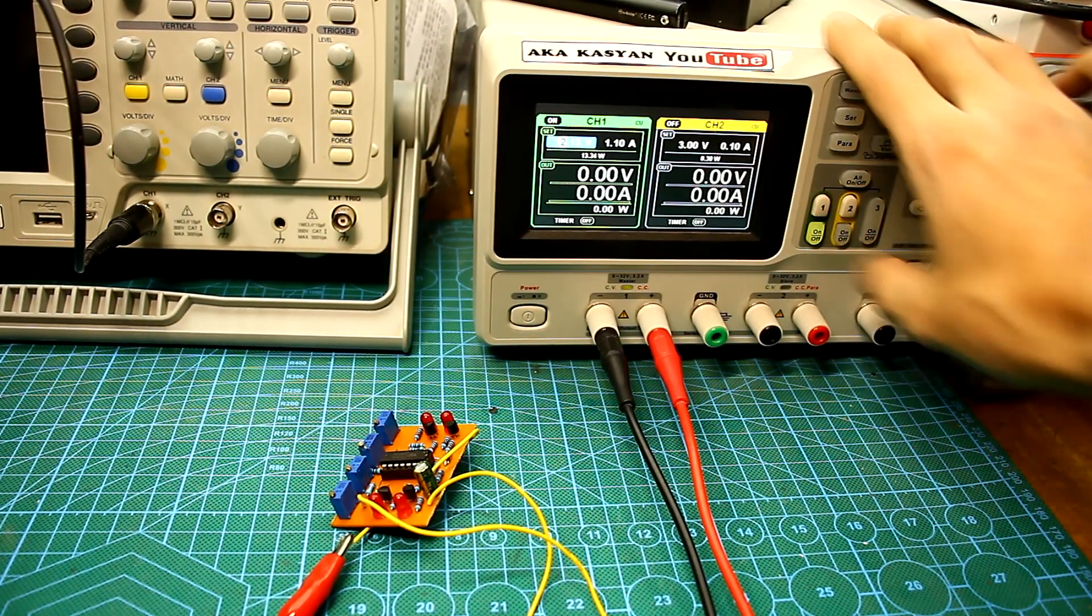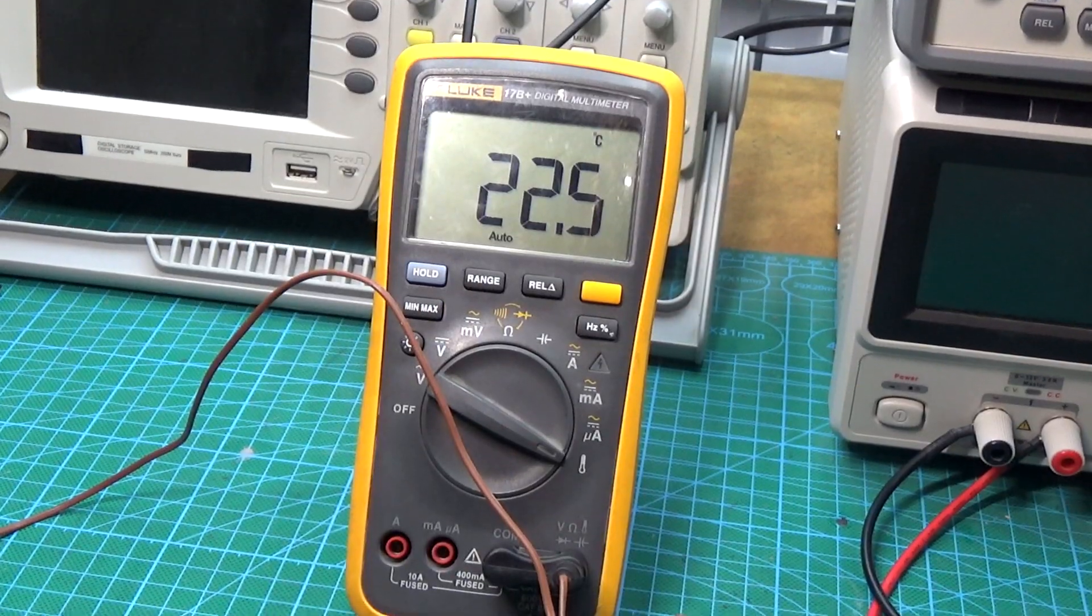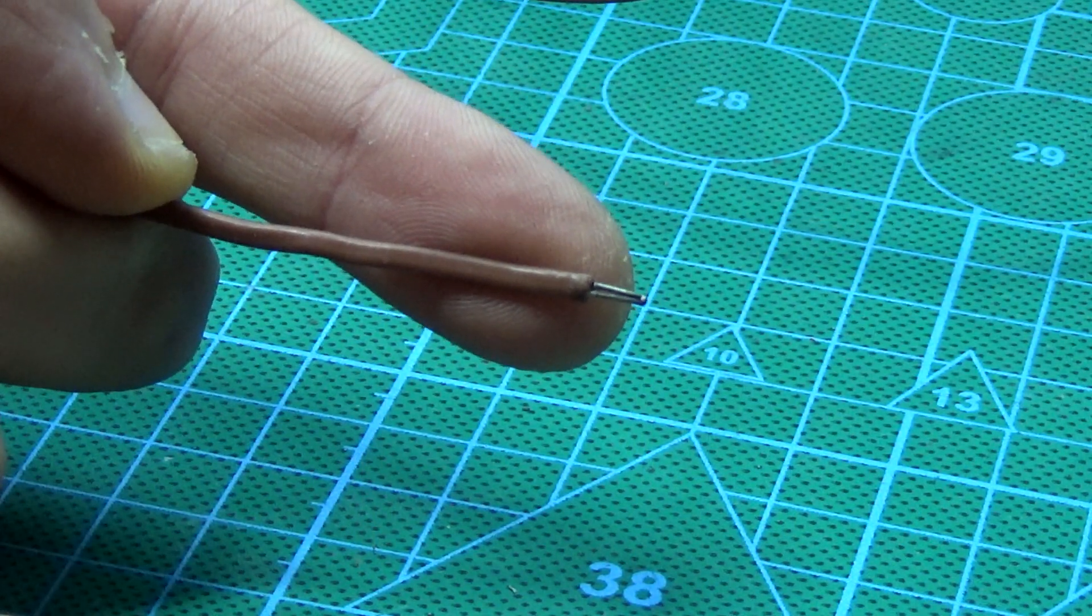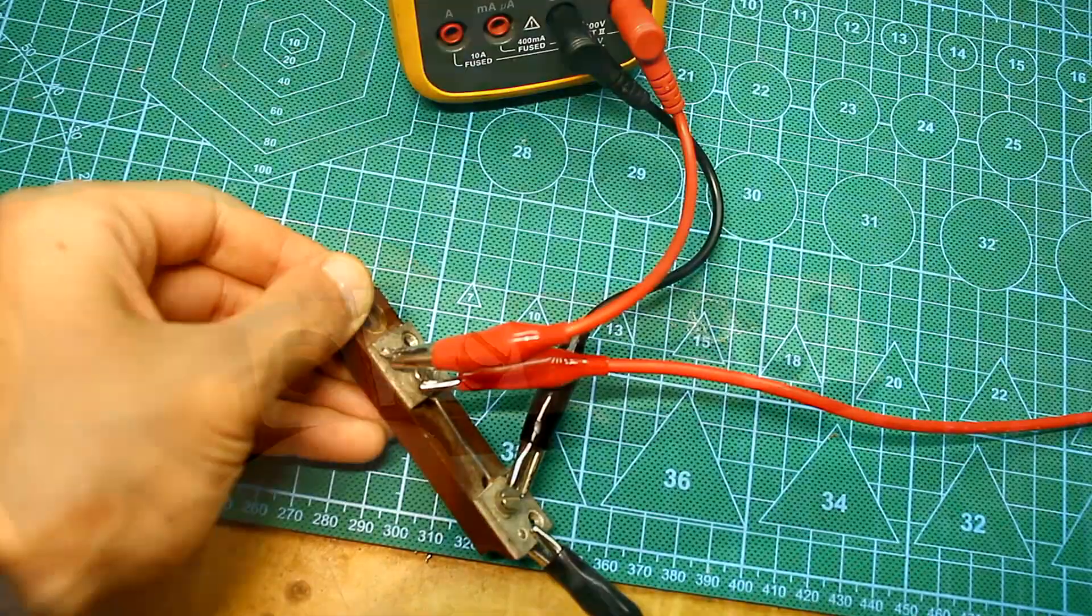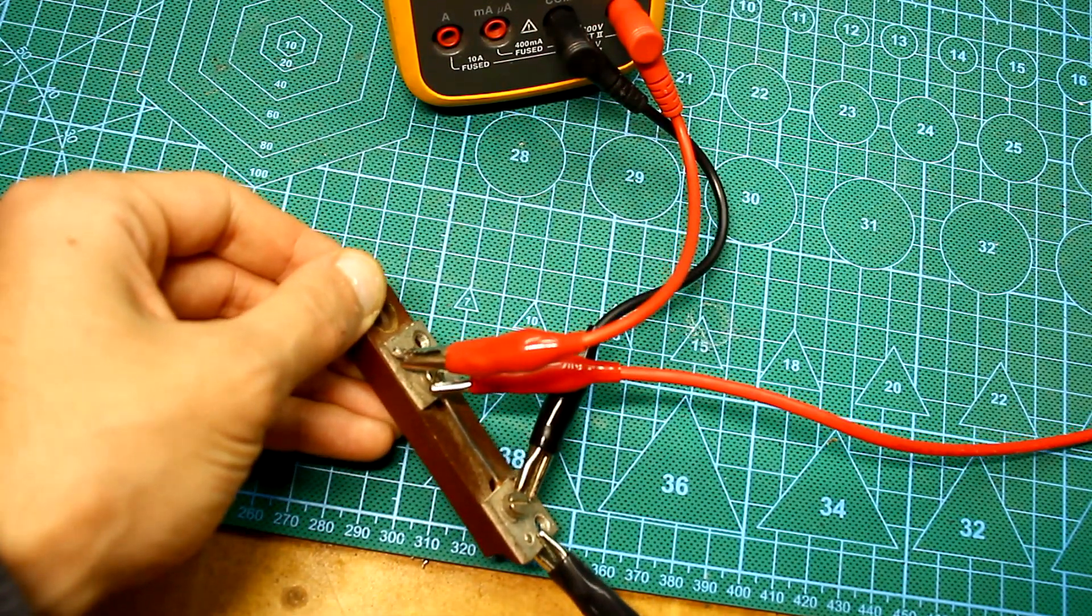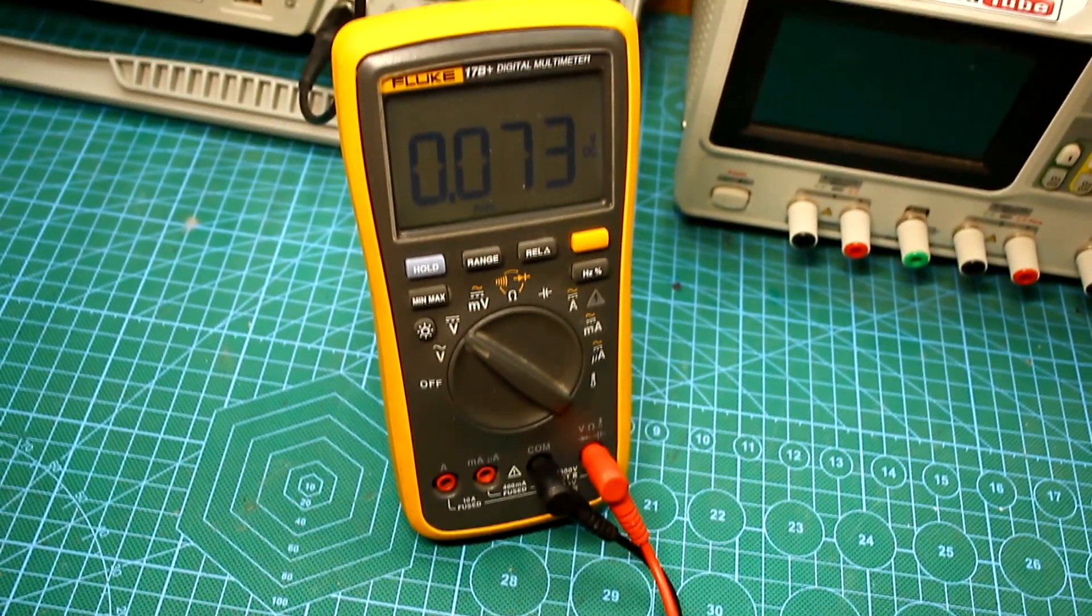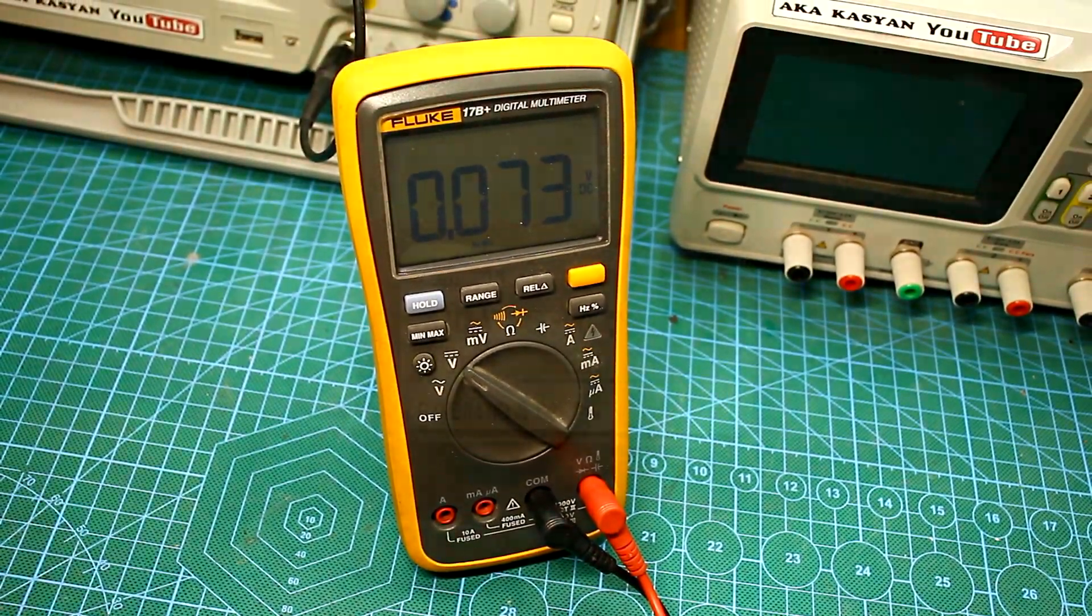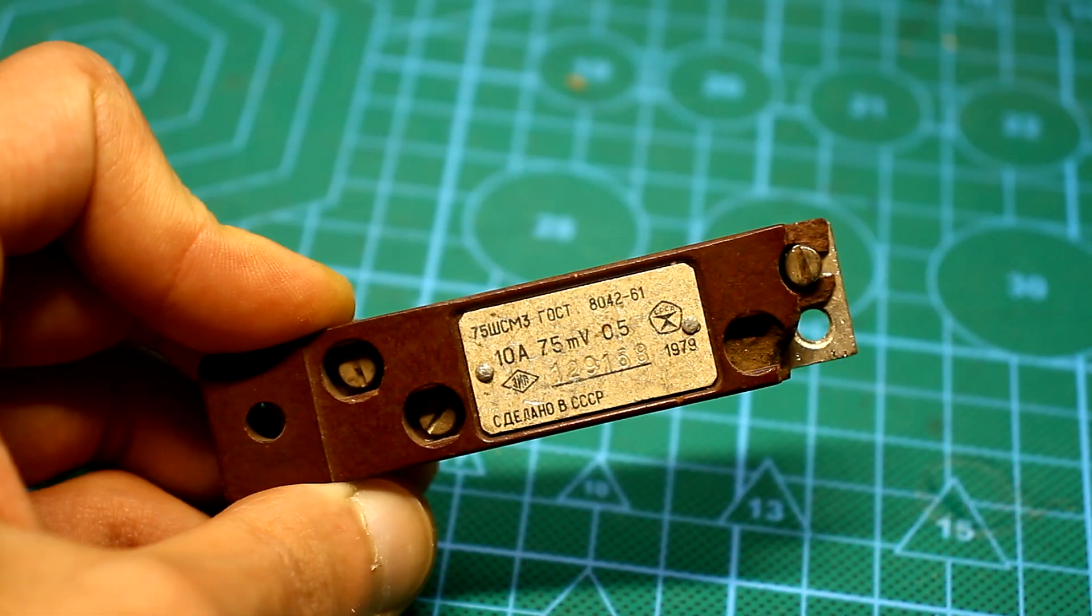Adjustment. For complete setup, you will need a laboratory power supply, an exemplary thermometer with a thermocouple and a current sensor. In my case, current sensor is a 10A shunt. When a current of 10A flows through it, the drop on the shunt will be 75mV. As a rule, most shunts have just such a drop. The difference can only be in the rated current.